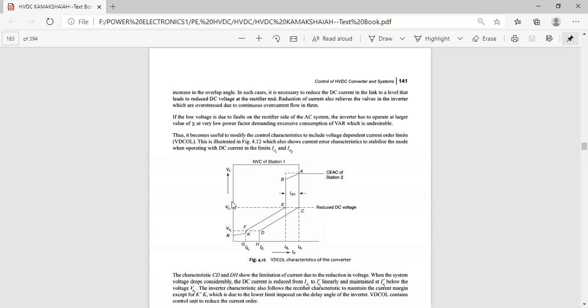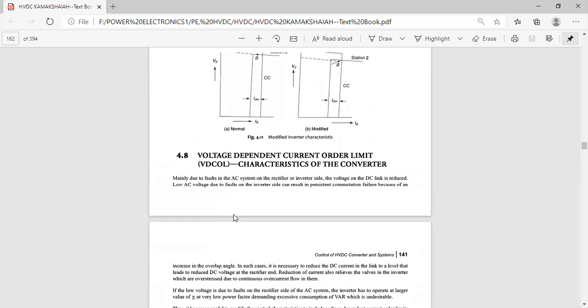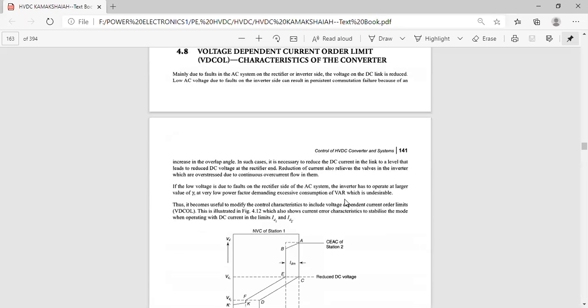If the voltage is reduced, the currents must also be reduced; otherwise the thyristors will be overloaded. The current margin Idm should remain the same or be less than the original value. For example, if Idm is 0.1 A and Idm-dash becomes 1.1 A, the thyristors will be overloaded and the circuit will be damaged. That is why we use the voltage dependent current order limit — the current order limit depends on the voltage.